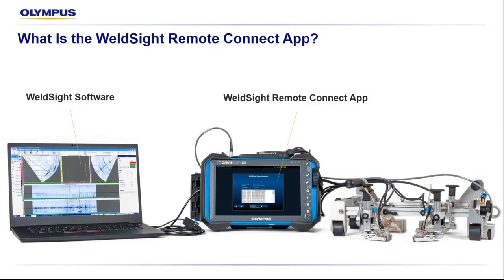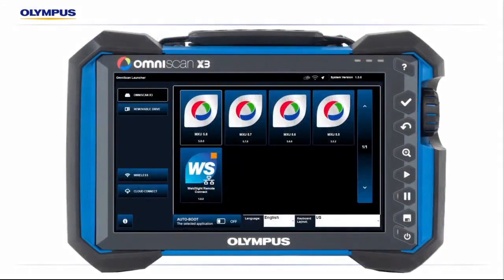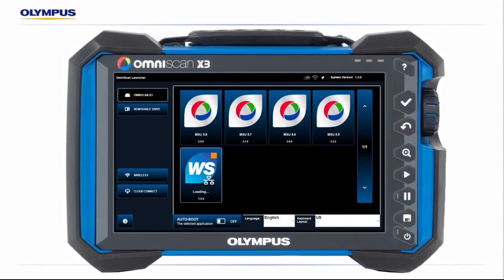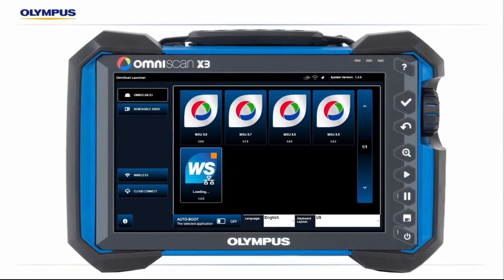The WeldSight Remote Connect application on the X3 allows for a seamless connection to a PC or laptop over Ethernet. This will turn the X3 into what's commonly known as a black box, allowing complete control of the inspection throughout the WeldSight software. Let's take a look at our WeldSight Remote Connect application. This is loaded on our OmniScan X3, just like a standard MXU software update. It can be loaded via USB or downloaded from our cloud through Wi-Fi. We'll launch that application, and that's going to pull us into our Remote Connect utility. This gives us basic information on connection status, our IP address, and start and stop acquisition. At this point, our OmniScan will be set aside and disregarded, and we will load our WeldSight software.